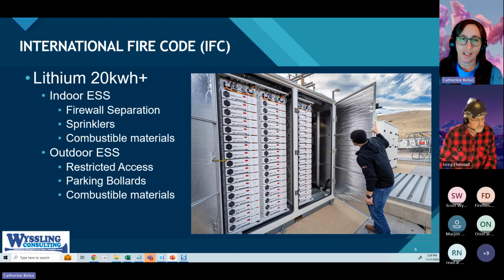If you put the energy storage system inside, you have to deal with firewall separations between the part of the building the battery is in versus occupied work centers. You need sprinkler systems in the building, and you must make sure there are no combustible materials anywhere near the battery system. A lot of times we realize that's going to be constrictive and make the installation very difficult.